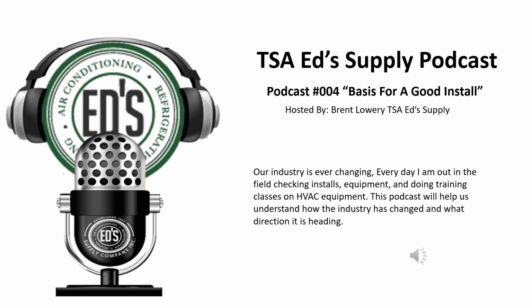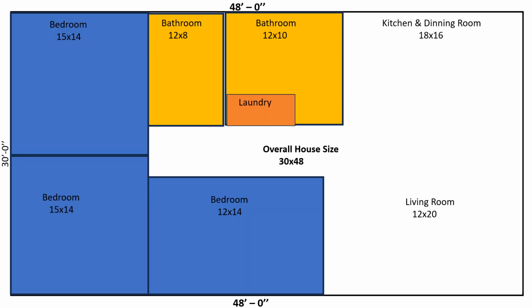But I've also learned a lot through this job about what ICP does, and we're going to talk about that. So let's take this house and look at it. If you're looking on the screen, you'll actually see this. Let's say this is a 3 bedroom house, just a standard 30 foot by 48 foot house, open concept when you walk in, and it had a 2 ton unit on it. If I look at the size of it, 30 by 48, that's 1,440 square feet.